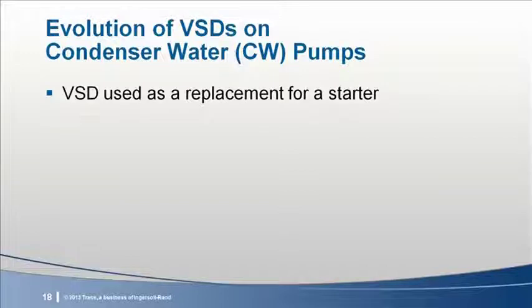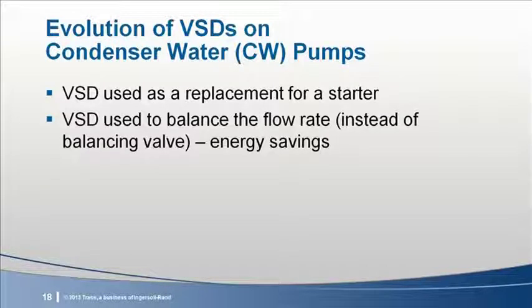Now, let's look at the condenser water pump. The marketplace seems to be moving toward installing variable speed drives in lieu of starters. Then, since the drive is there, rather than using throttling valves, that VFD is used to balance the system, and there are energy savings since pump pressure is not being wasted by throttling.